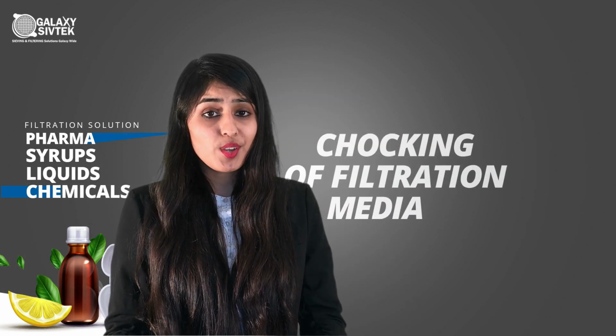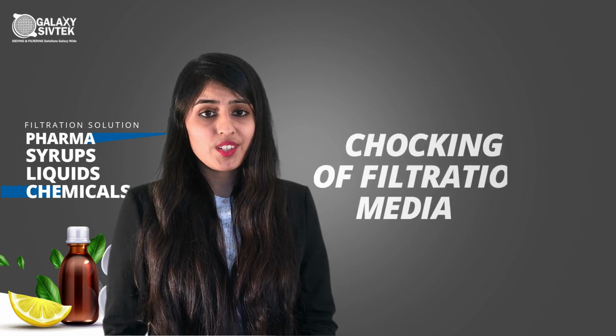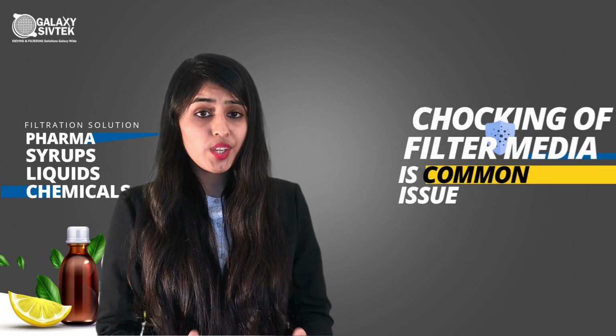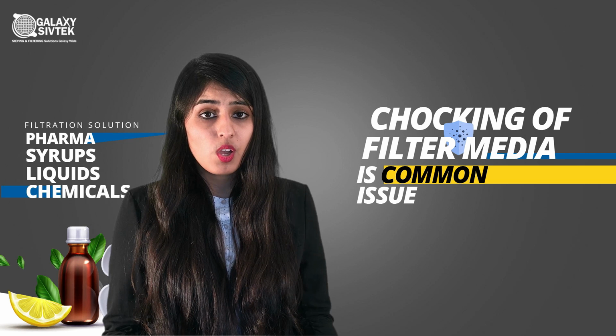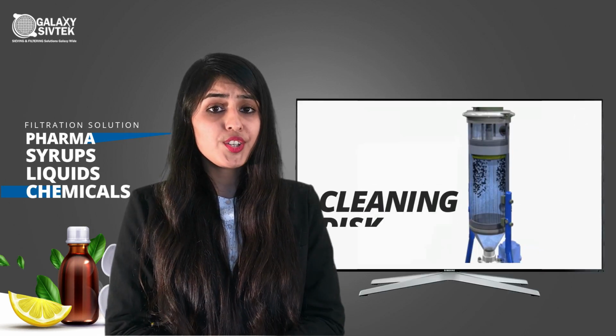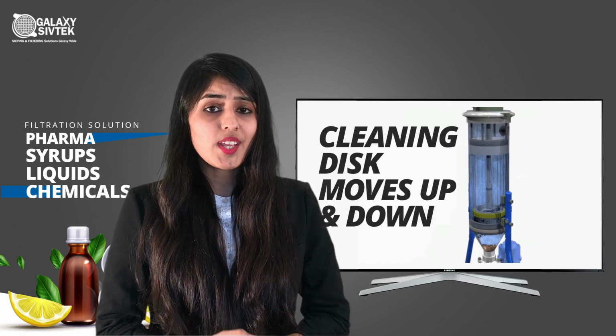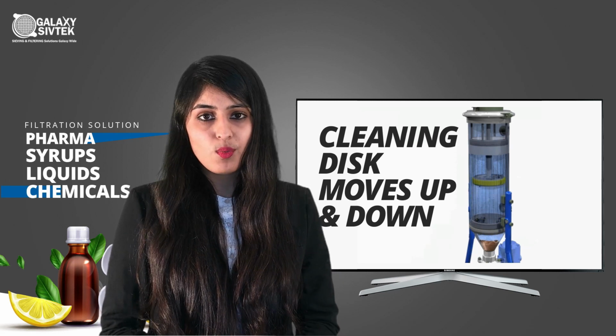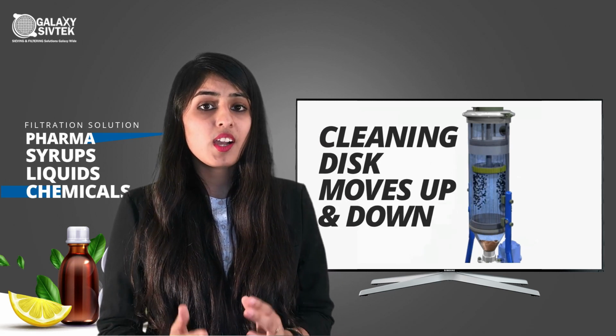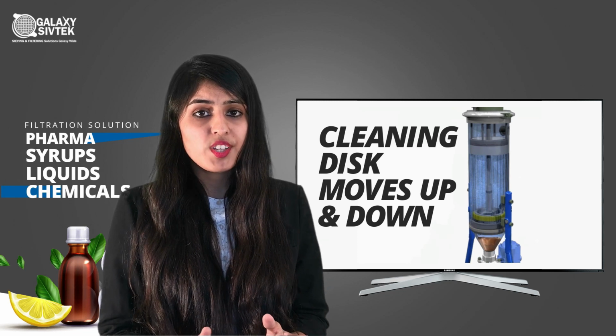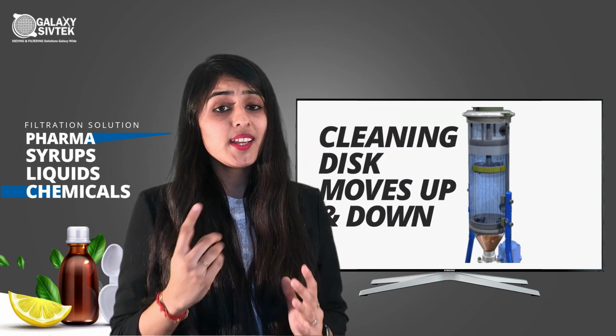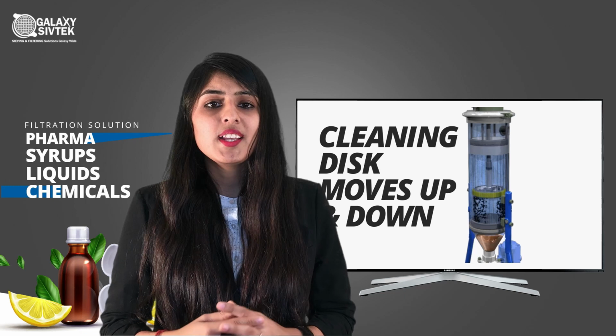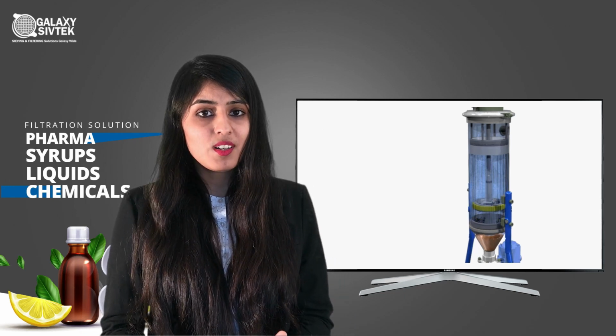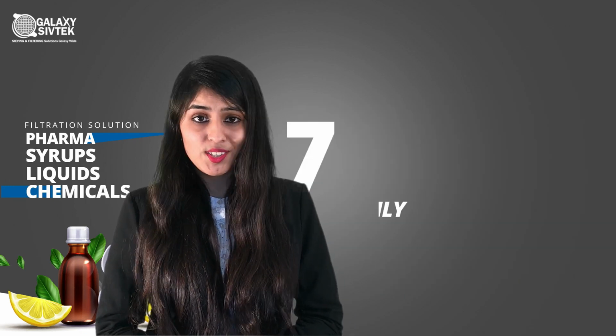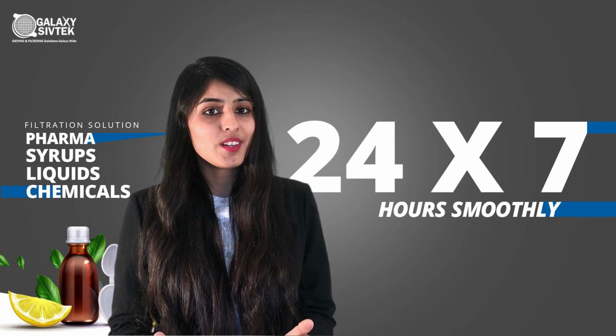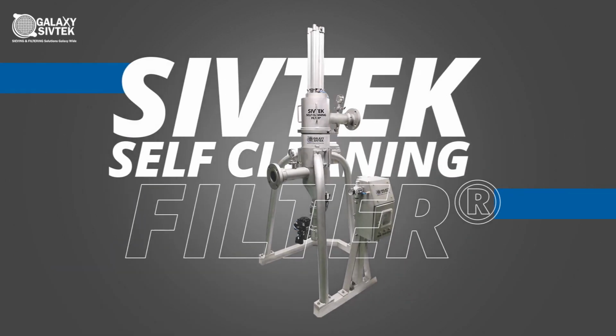Reason number one: choking of filtration media. With most filtration systems, it's generally observed that choking of the filtration media is a common issue, which needs to be cleaned manually by halting the ongoing process. But with a self-cleaning filter, the filter basket which acts as the filter media is accommodated by a cleaning disc which moves up and down inside the inner periphery of the basket, cleaning any impurities or oversized material residing over it. This means there's no mass choking, and your filter runs 24/7 smoothly.